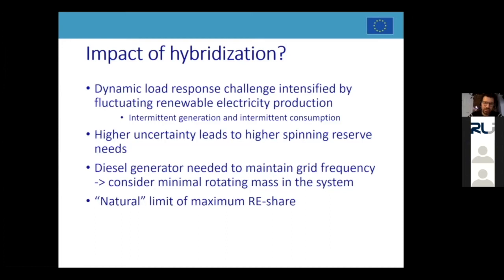This leads, for example, to higher spinning reserve needs, so hybridization causes a bit more stress on the diesel plants. The diesel generator still needs to maintain the grid frequency if combined with a PV system, so there must be a minimum share of rotating mass in the system. Based on this increased complexity and stability criteria, there's what we call the natural limit of a maximum RE share if we don't have batteries.